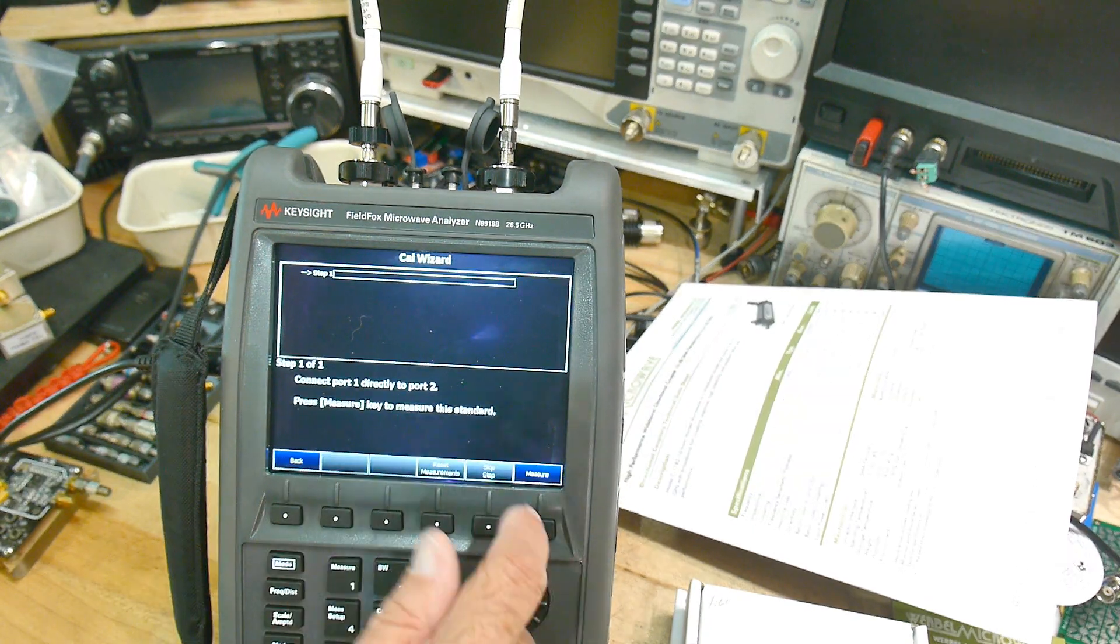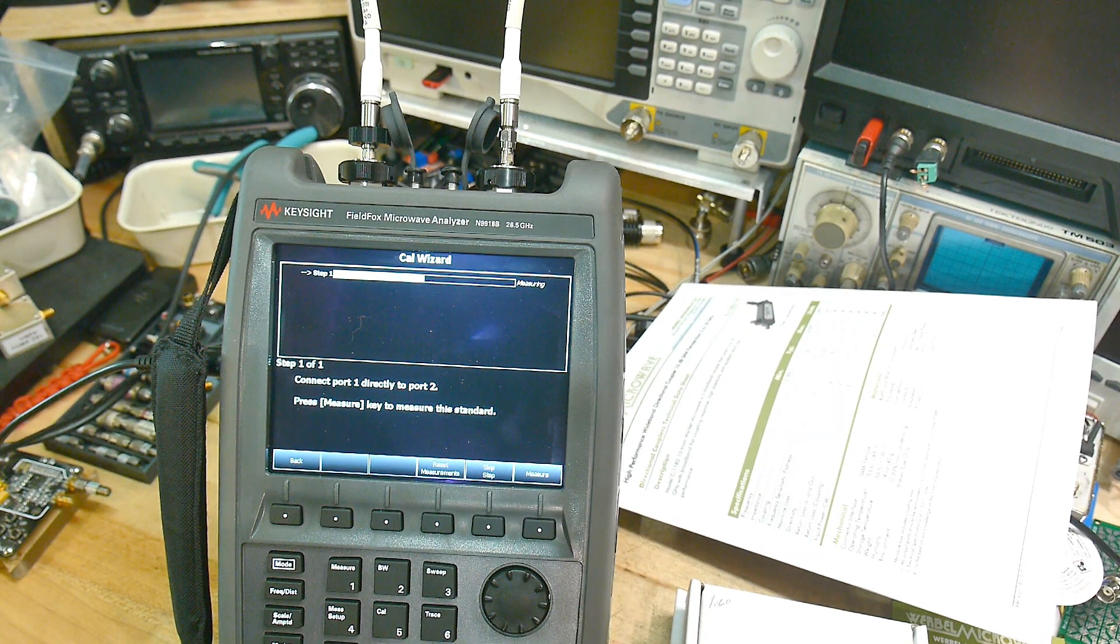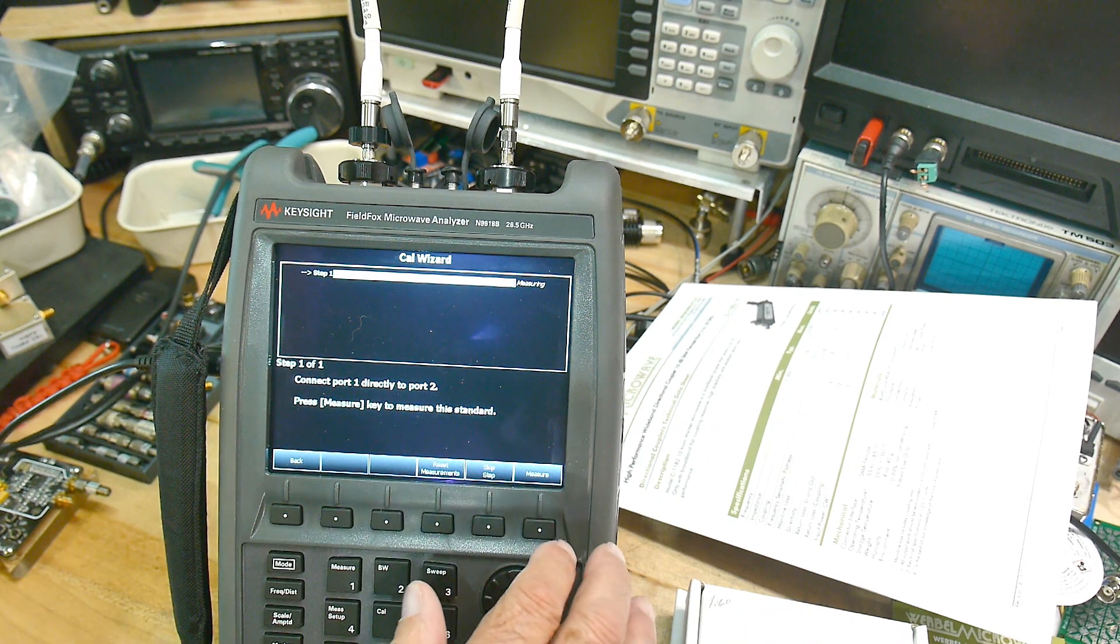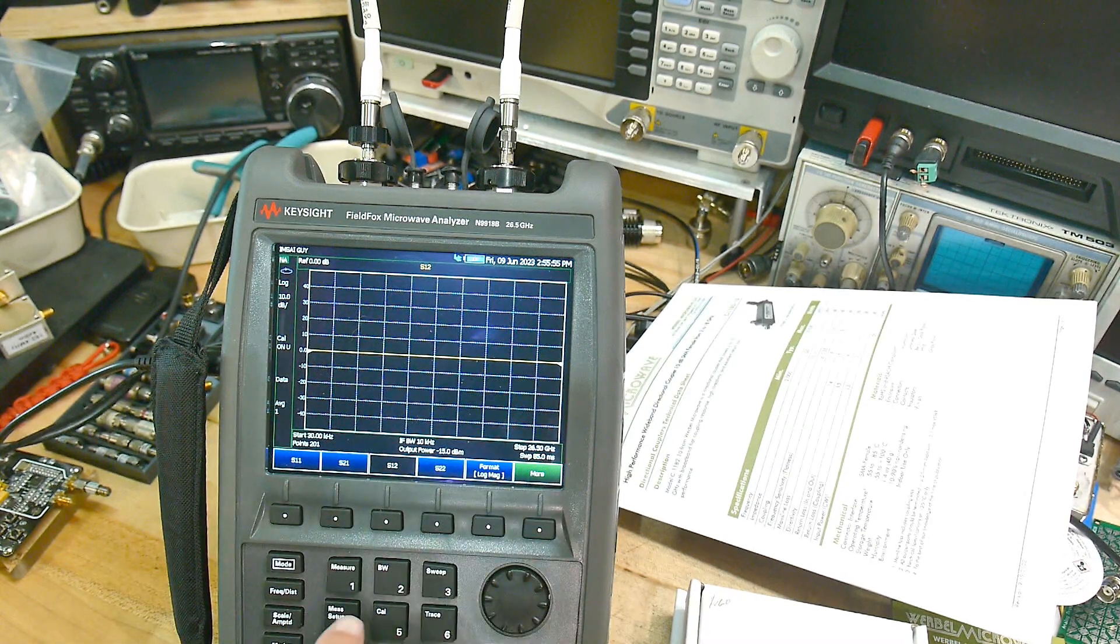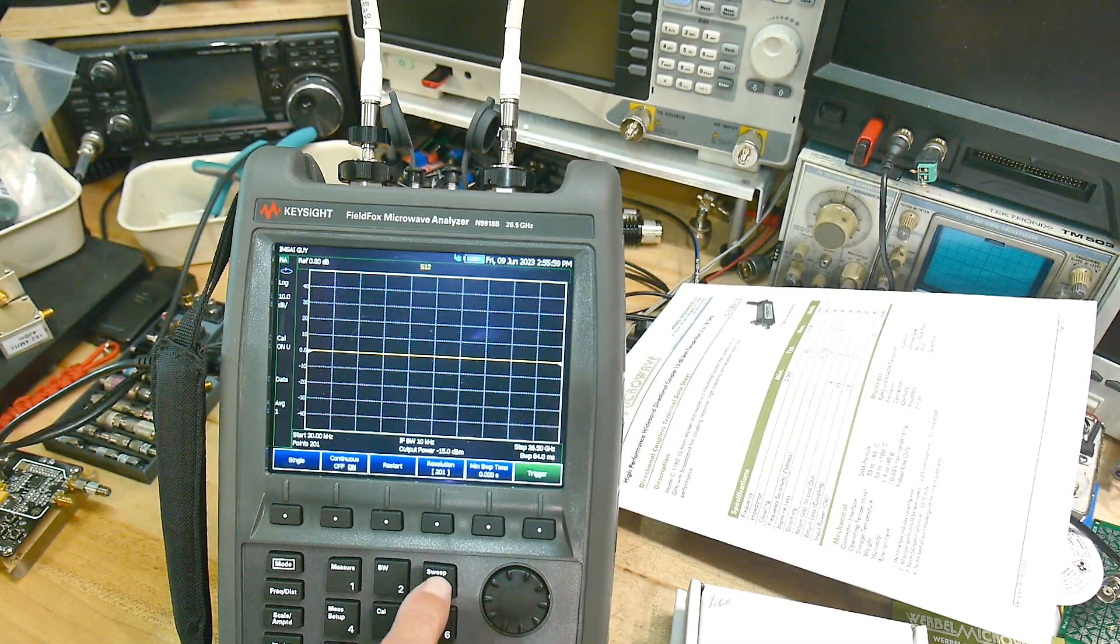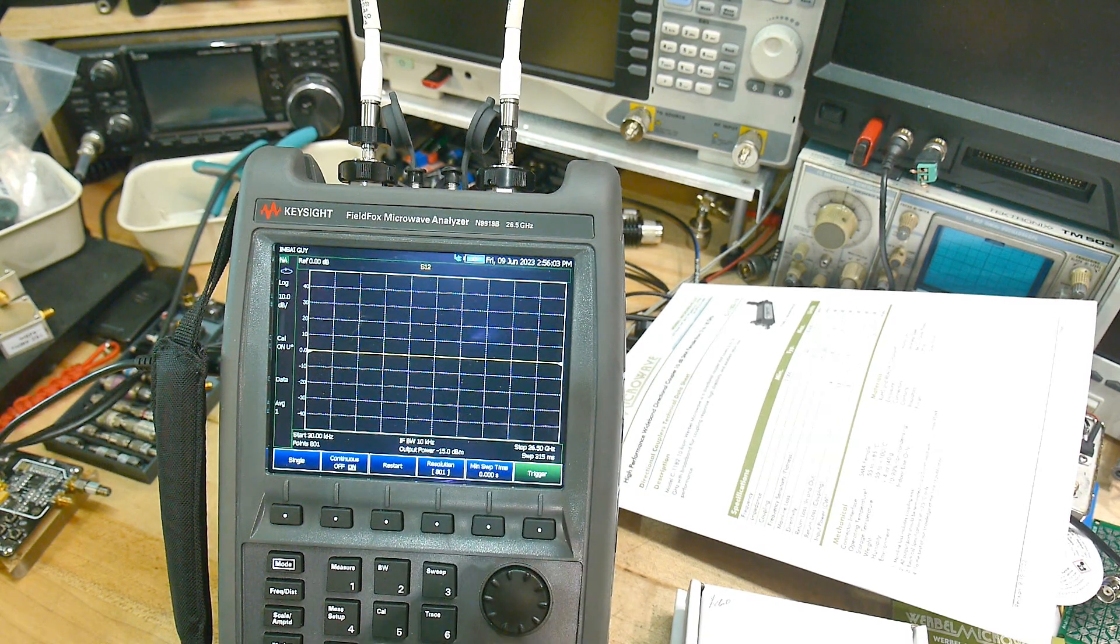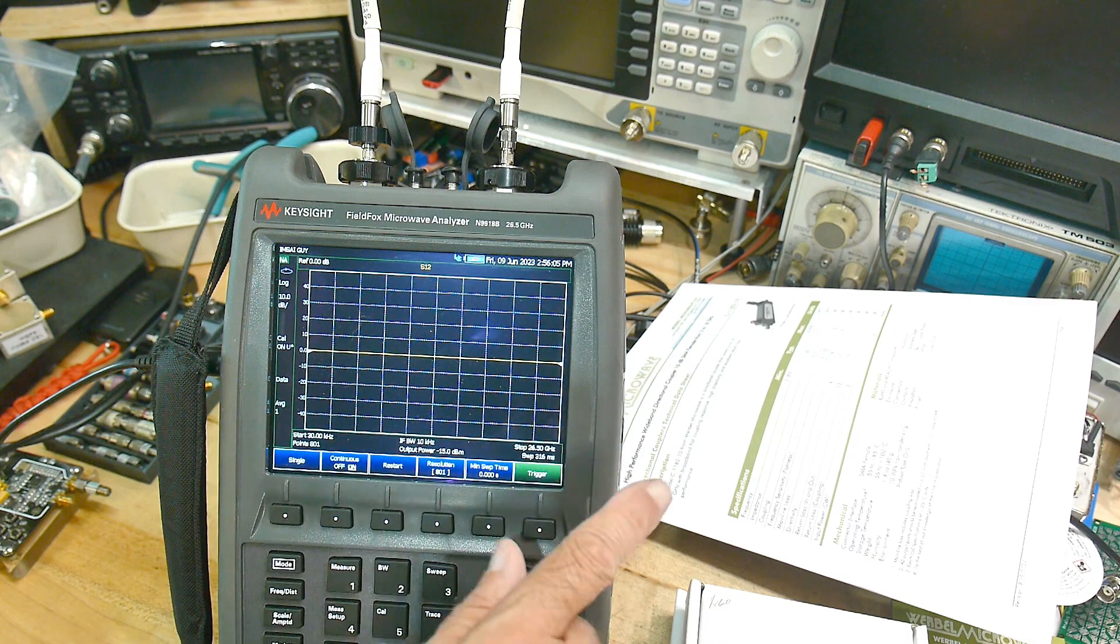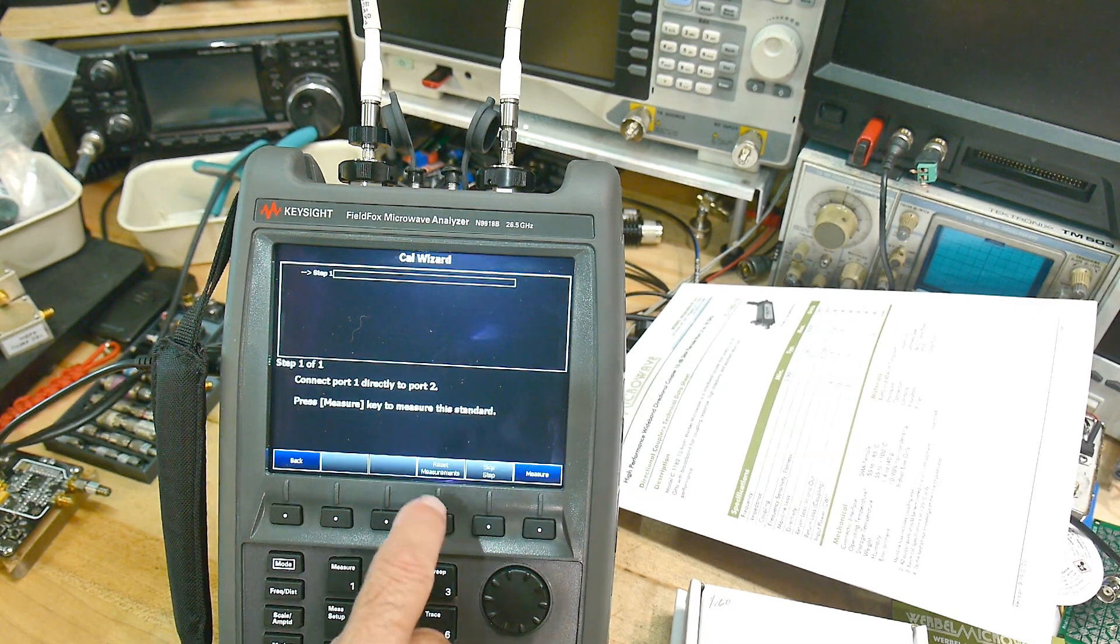Let me set the number of steps. We have a lot of steps here. Let me go back and make sure the steps are good. Let's see, measure setup. Where is it? Trace, yeah, sweep. Resolution 201, yeah, let's do 801. 801 steps across. Let's go back and recal it for that.